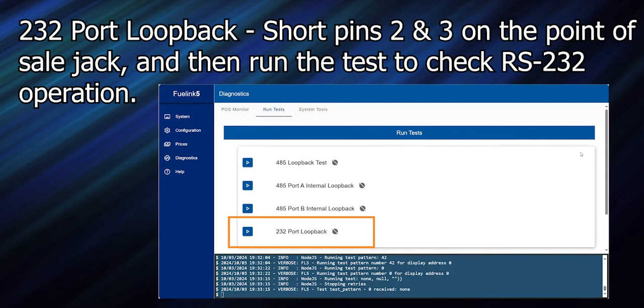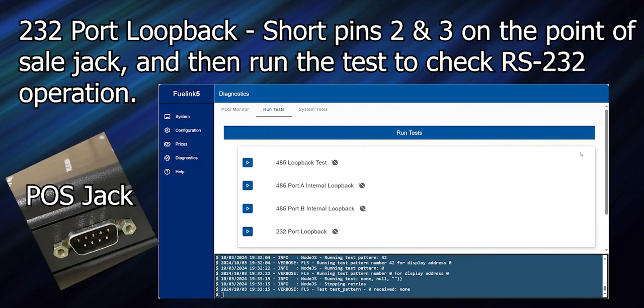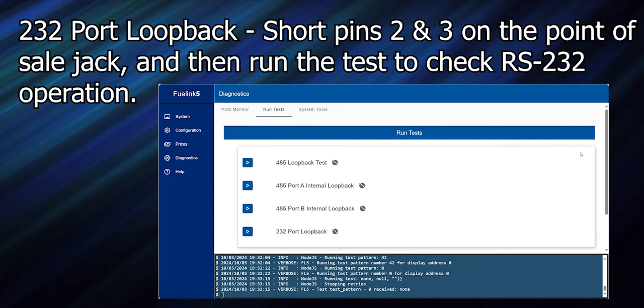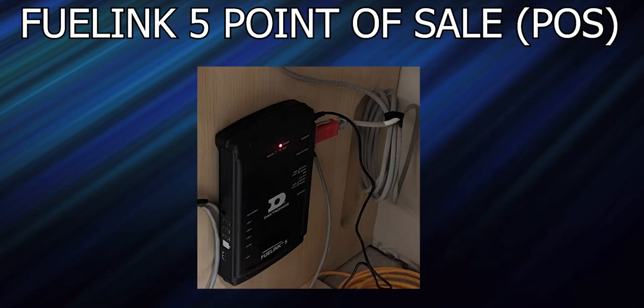The other option is the 232 port loopback. For this test, you will first short pins 2 and 3 on the point of sale jack, and then select to run the test to check the RS-232 operation. And that wraps up installing and testing the point of sale interface with the FUELINK5 setup.